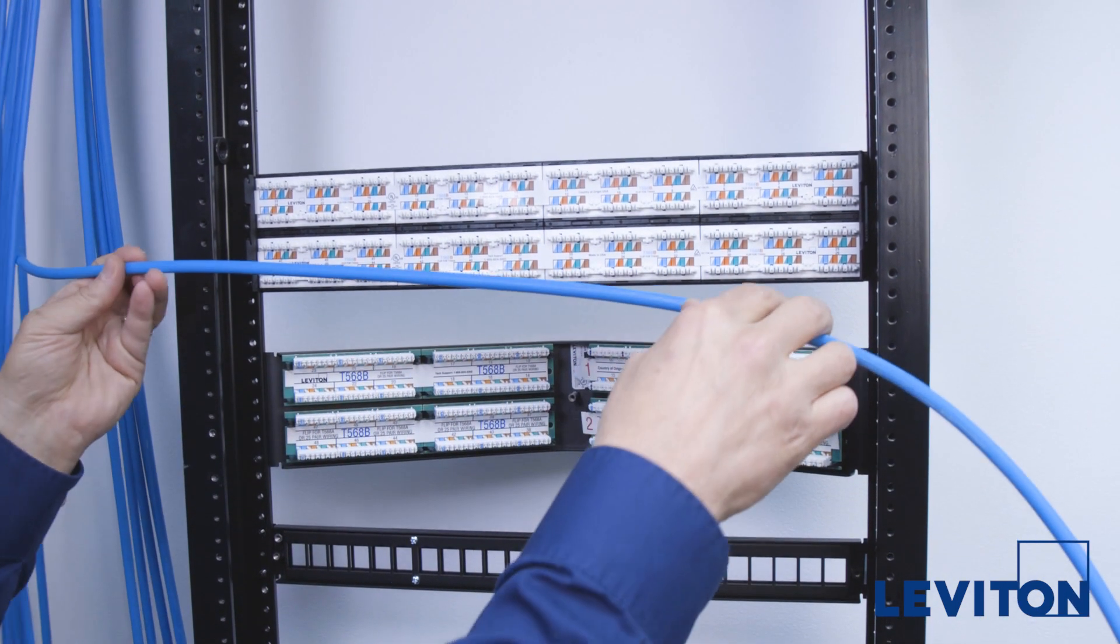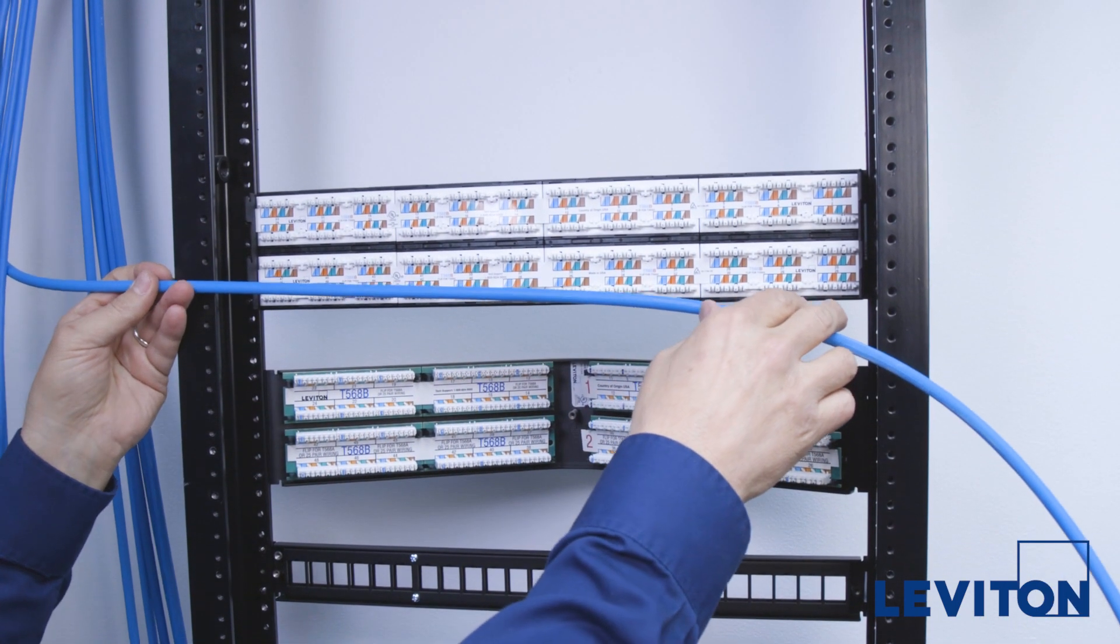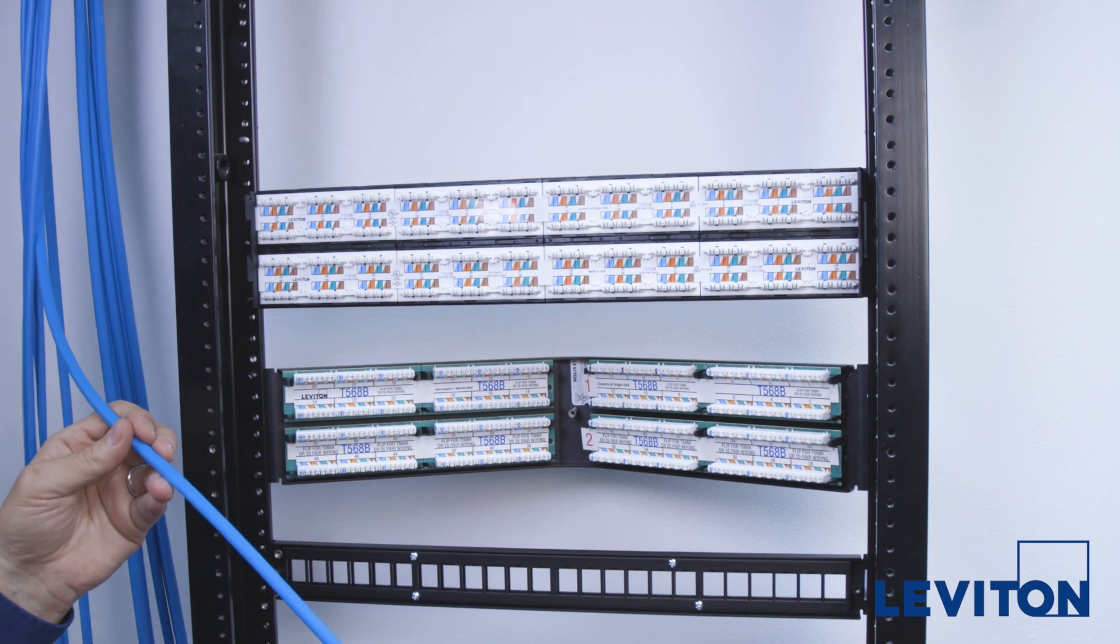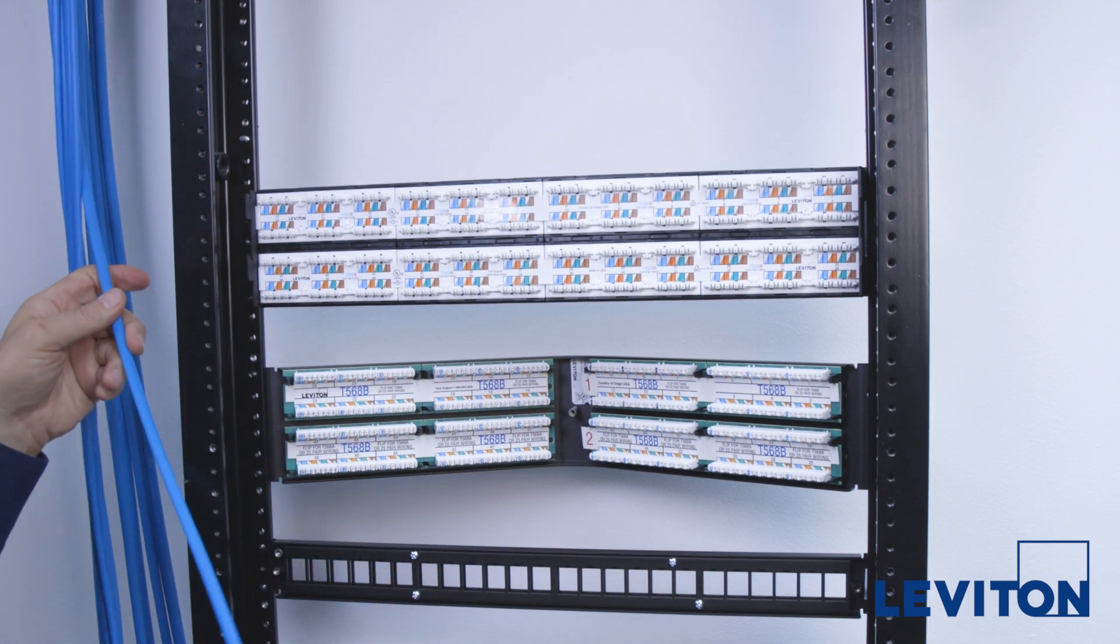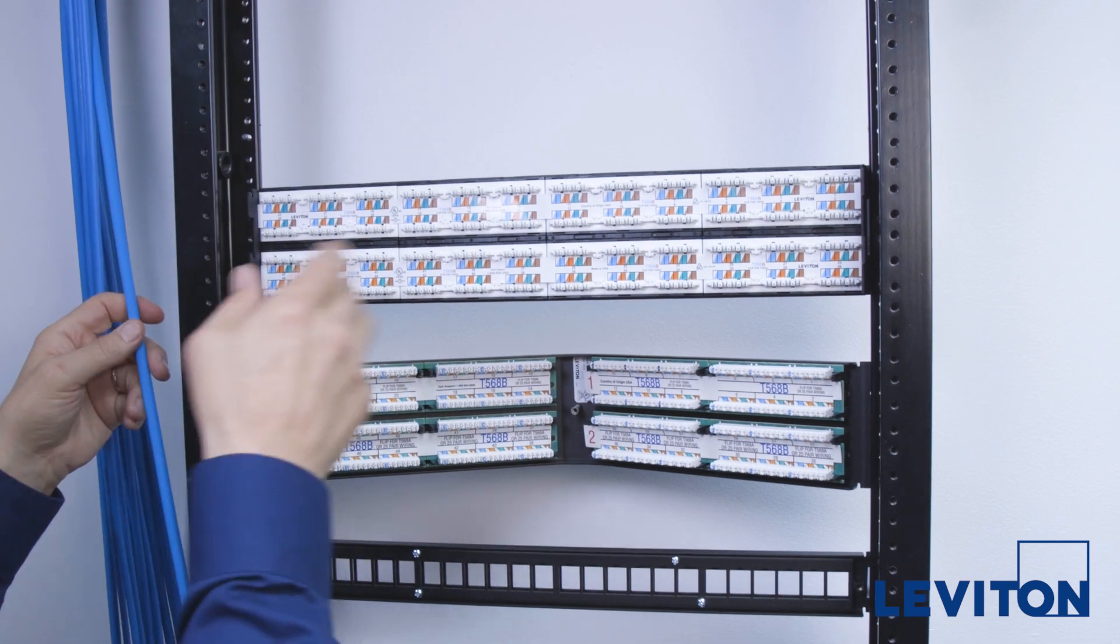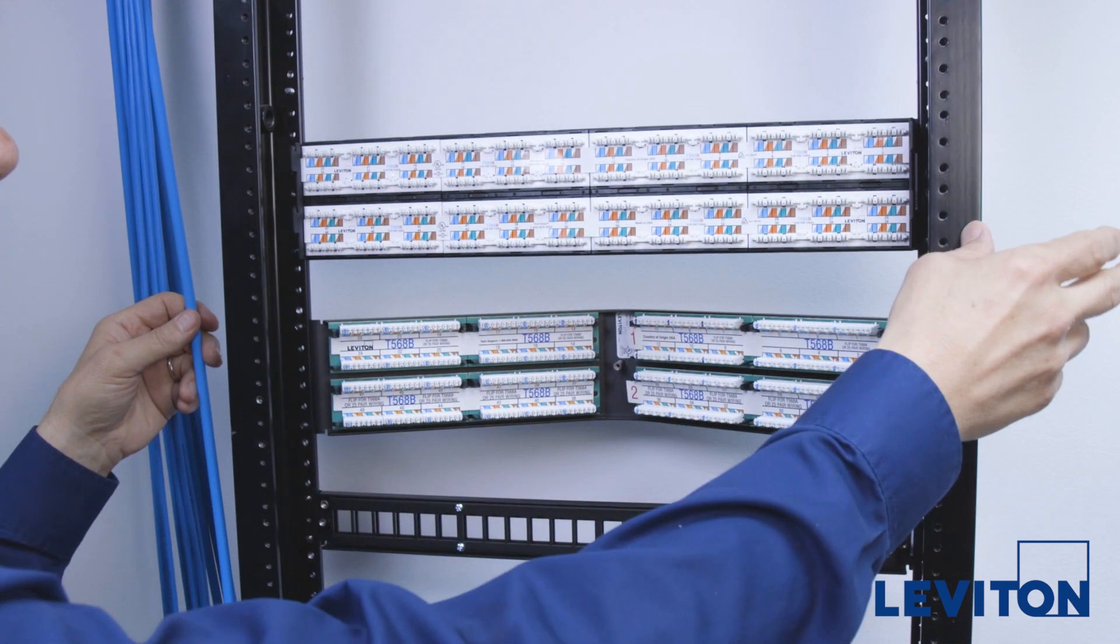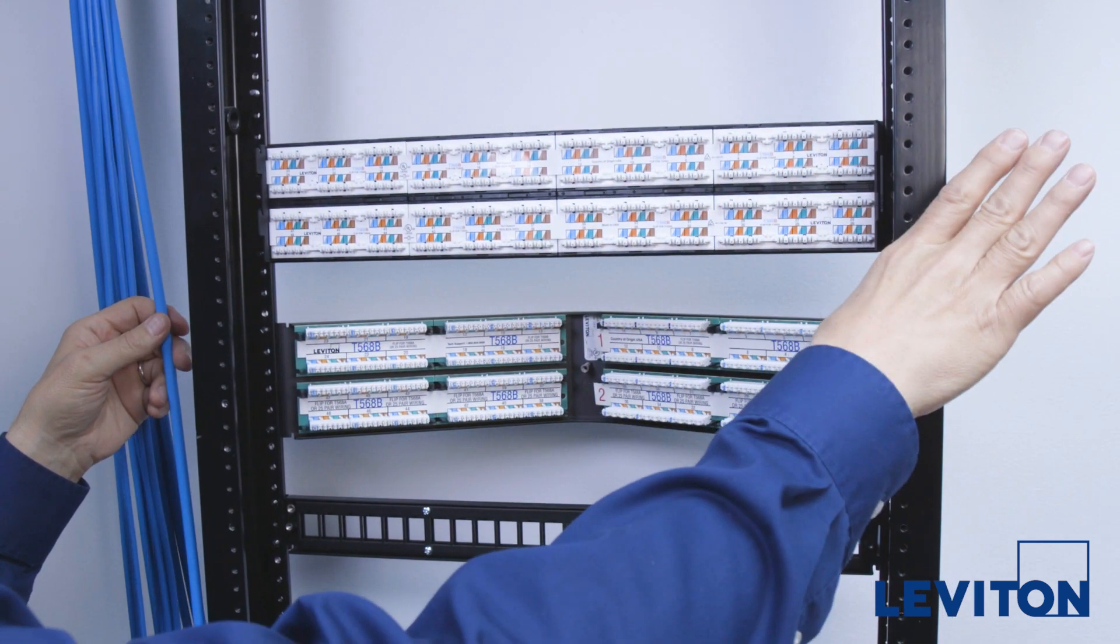Due to the larger size of Category 6A cables, you cannot run wiring from a single side of the rack. Instead, terminate the cable running down the left-hand side of the rack from the center of the patch panel out toward the left, and the cabling running down the right-hand side of the rack from the center out toward the right.